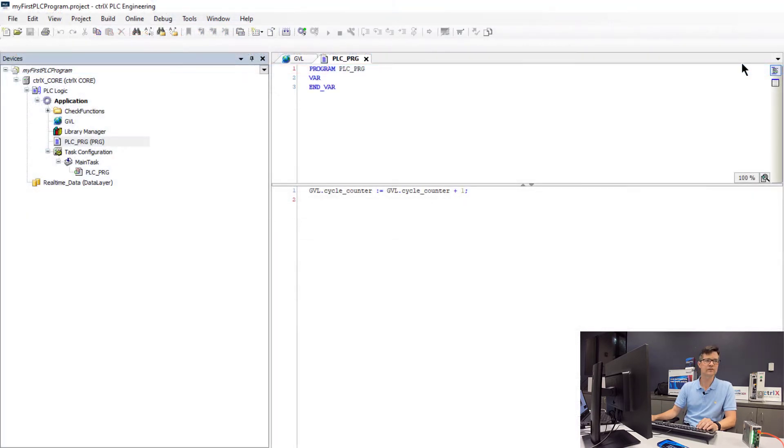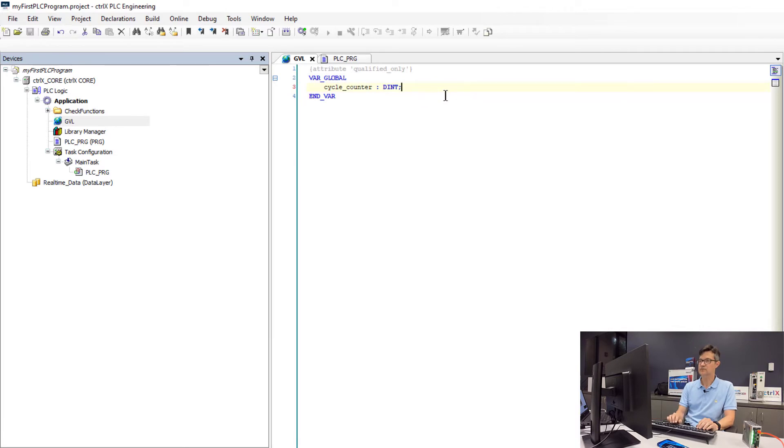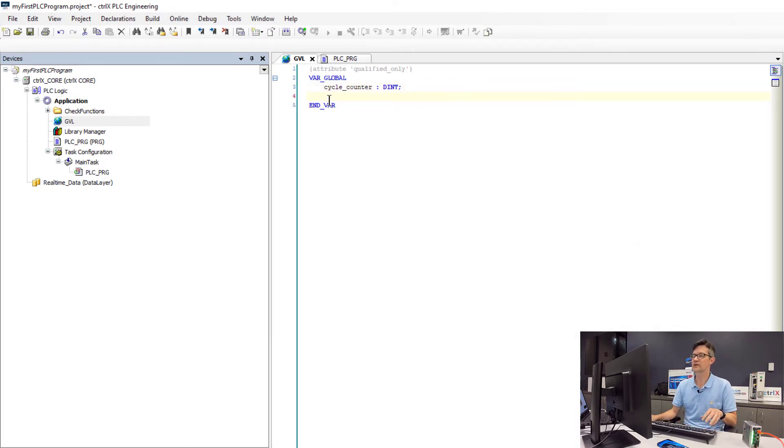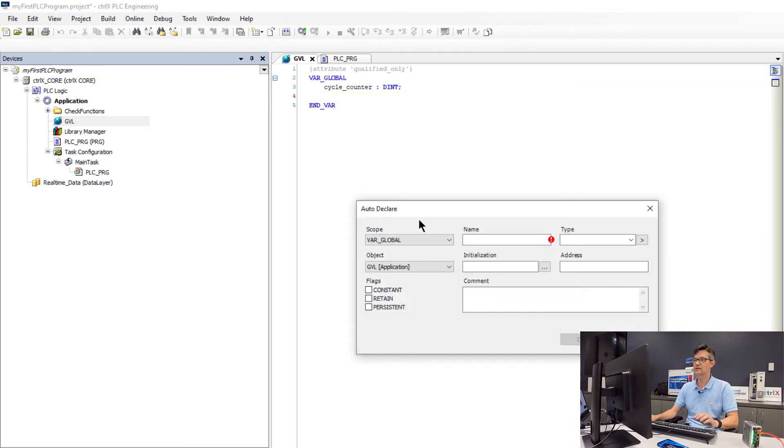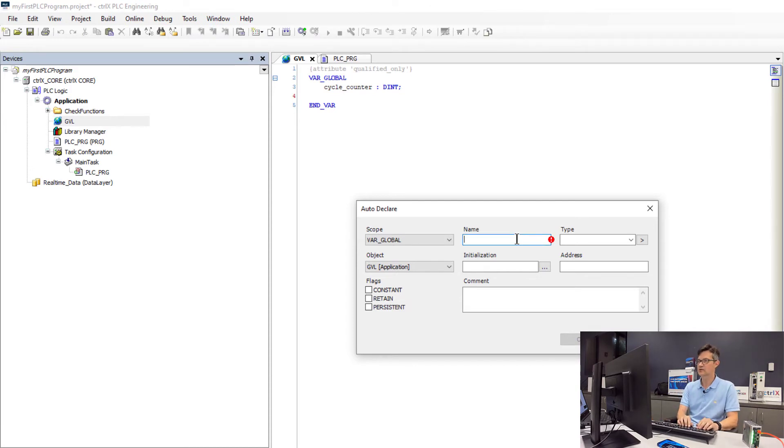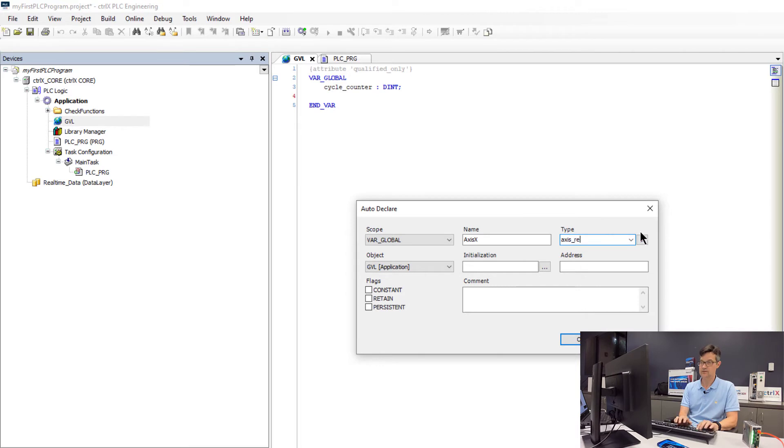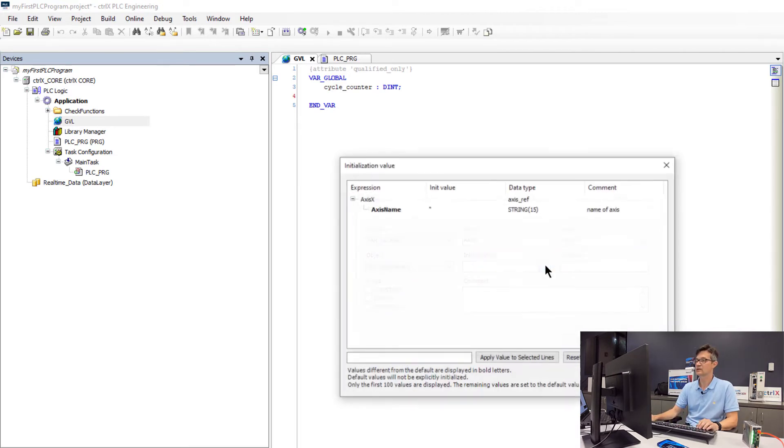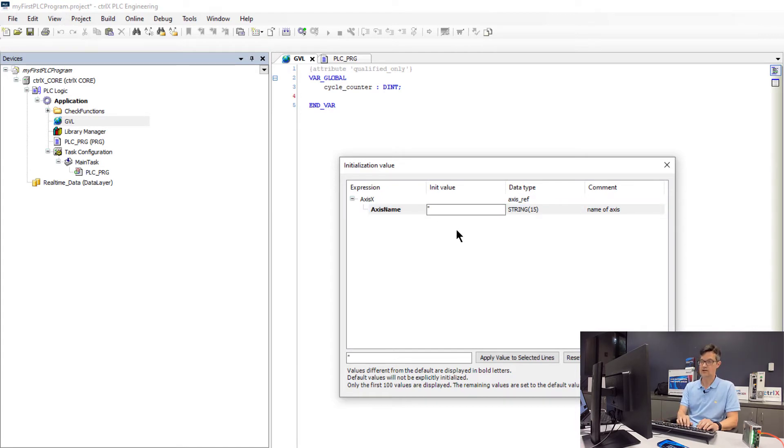The first thing that we will do is go back into the global variable area and we will define our Axis ref variables. A simple way to declare your variables quickly is to use an auto declare with the Shift F2 key. I will declare my Axis names with this wizard. So Axis X of type Axis ref. We will use for the initialization, we have to initialize the name of our axes using a string with the same name that we had configured in the Motion app.